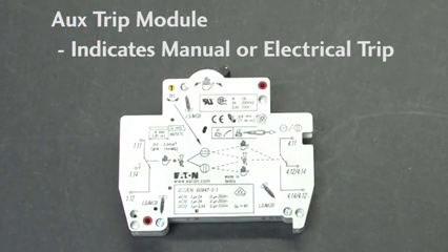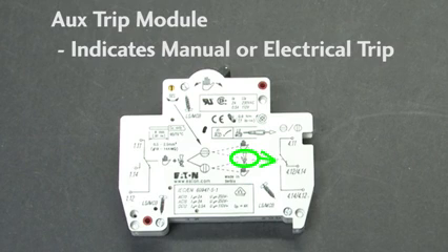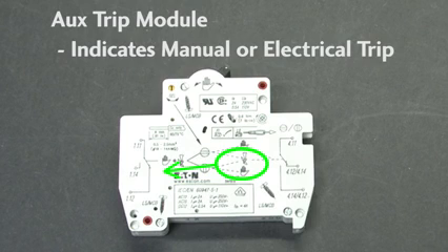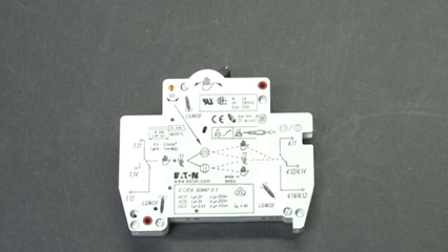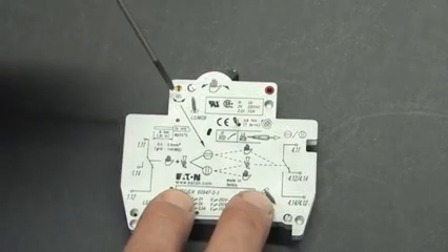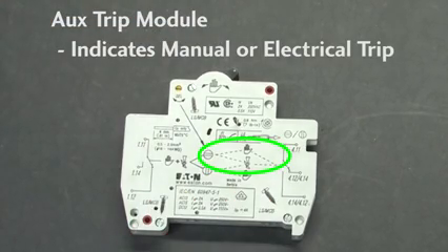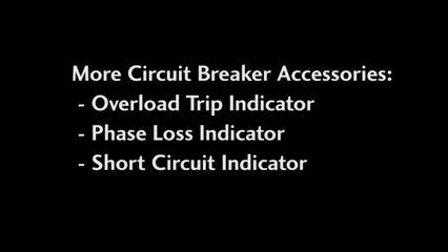This aux contact is a little different because it can detect if the breaker was tripped manually or electrically. This set of contacts tells you if it was tripped electrically, and this set tells you if it was tripped by either. Connect those to PLC inputs, and now the PLC can tell what caused the breaker to trip, a fault or a coworker. If I rotate this little switch right here, now both sets of contacts trip on either manual or electrical faults. Cool. There are a number of other accessories that can tell you if the breaker tripped due to overload, phase loss, short circuit, etc. The point here is there are lots of ways circuit breakers and their accessories can help you quickly diagnose the problems in your system. So check them out. They can save you a lot of time, money, and headaches in the long run.